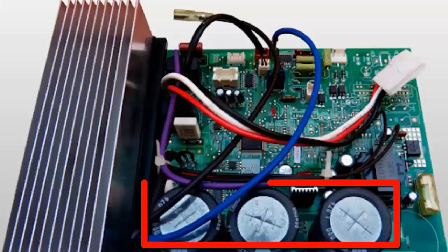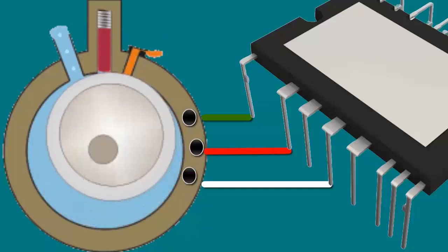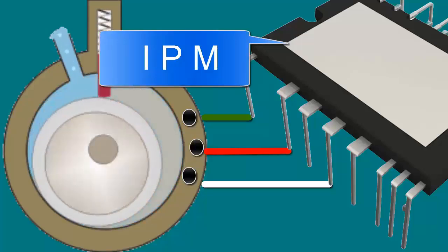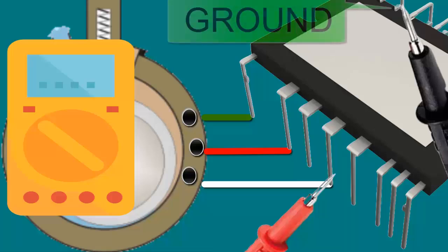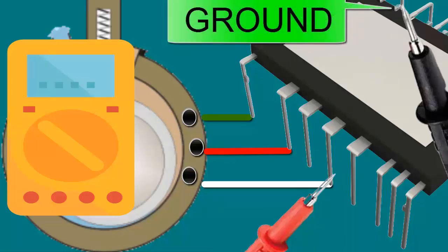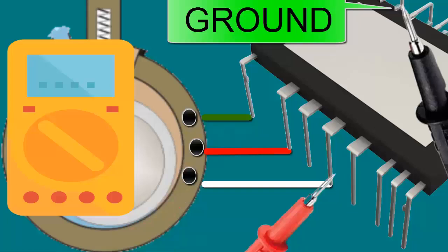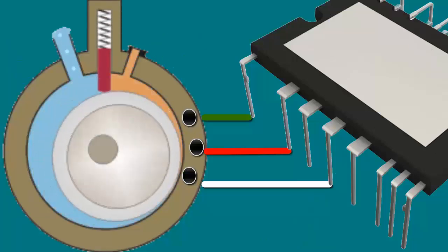To check for faults in the IPM module, first disconnect the unit's power supply. Remember that electrolytic capacitors can store energy. The most common test is to perform a visual inspection for faults and use the multimeter on the high resistance scale, placing the negative probe on the IPM module circuit ground and the positive probe on any of the IPM module terminals that go to the compressor. You should get an infinite reading, indicating no short circuits.